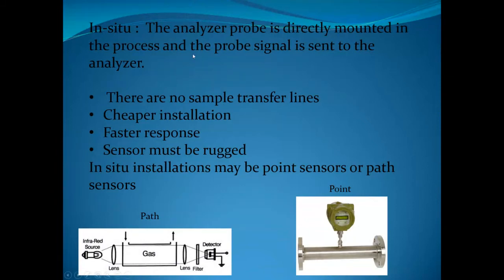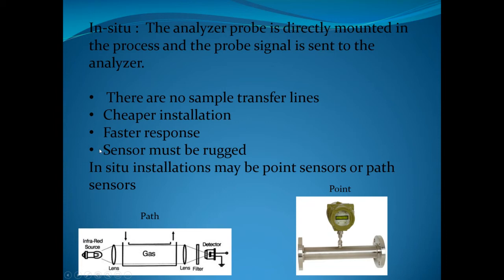For in-situ specifically, the probe is directly mounted in the process. Benefits include no sample transfer lines, so no pluggage risk, lower cost, and faster response because the sensor is right there at the process. The downside is the sensor must be rugged enough for the field environment — temperature, weather, vibrations. In-situ sensors may also be point sensors or path sensors; path sensors use a transmitter on one side and receiver on the other, shining infrared light through the sample and measuring the absorbed difference.